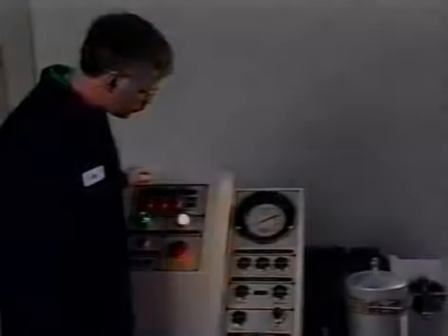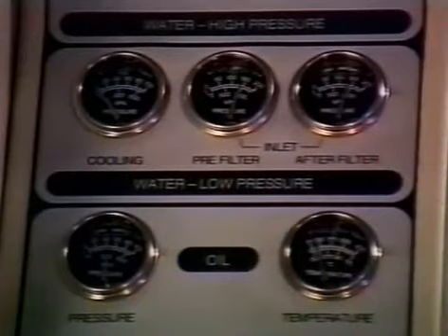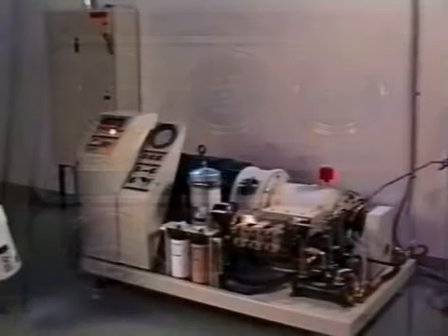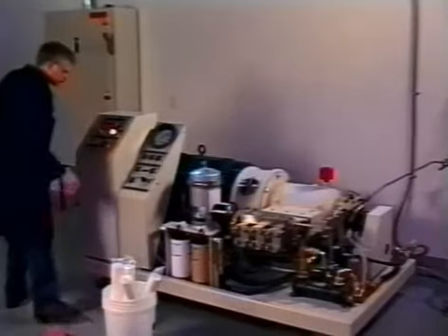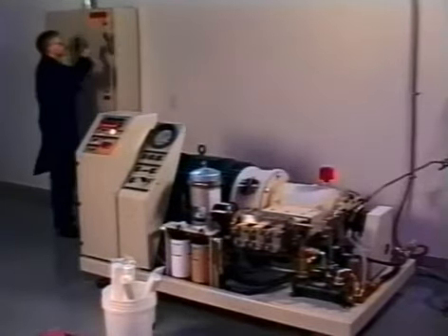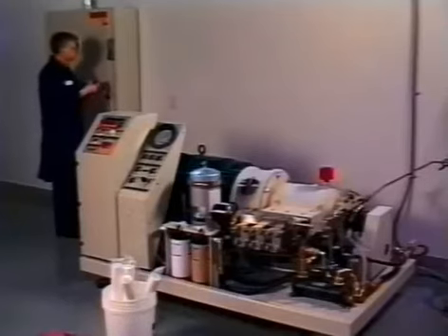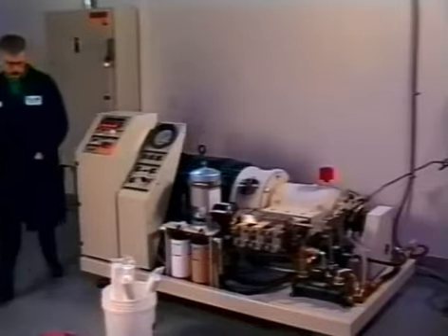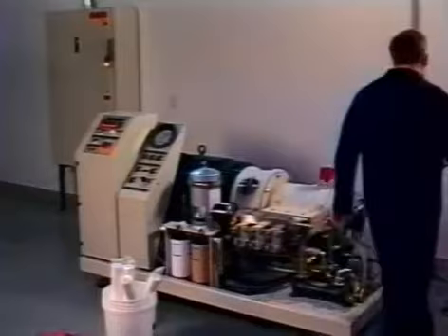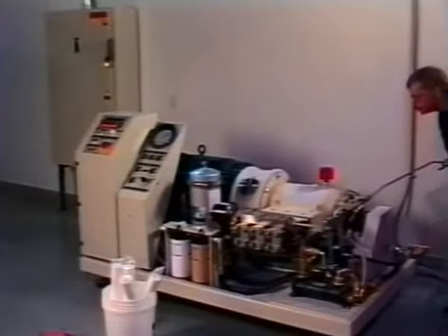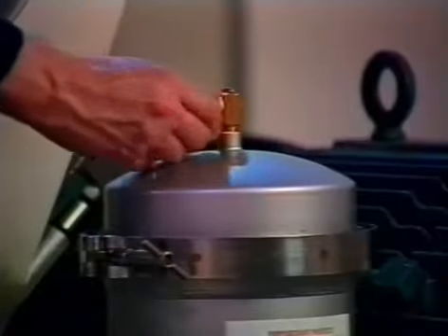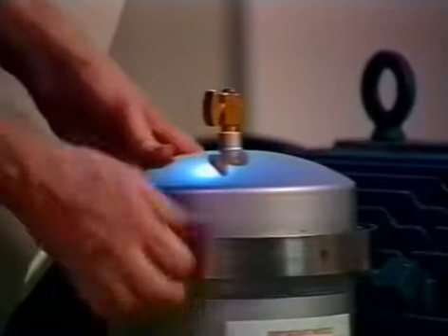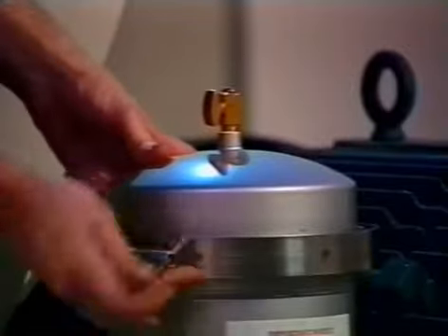Changing inlet water filters. The inlet water filters must be changed before the difference between the pre-filter and after-filter gauges exceeds 60 psi. To change the filters, first shut off the incoming water, then open the vent on top of the filter housing. For diesel pumps only, drain the filter housing by opening the ball valve on the bottom of the filter housing.